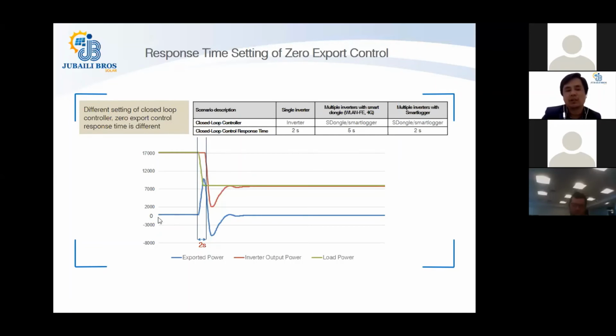So in that scenario, the exported power, the blue line, is always zero. At some point, when one of the loads goes down, which is the light green, at this point it goes down, for a very short instance there will be some power exported towards the grid till the inverter detects that there is excess generation going towards the grid, and it reacts against that. That whole period takes around 2 seconds. This is true for the single inverter and the multiple inverter with the smart meter. And again, after 2 seconds, it will come back to the point where it is giving zero power toward the grid side. It may go below zero for a very short moment, but again it will get itself stable within 2 seconds.